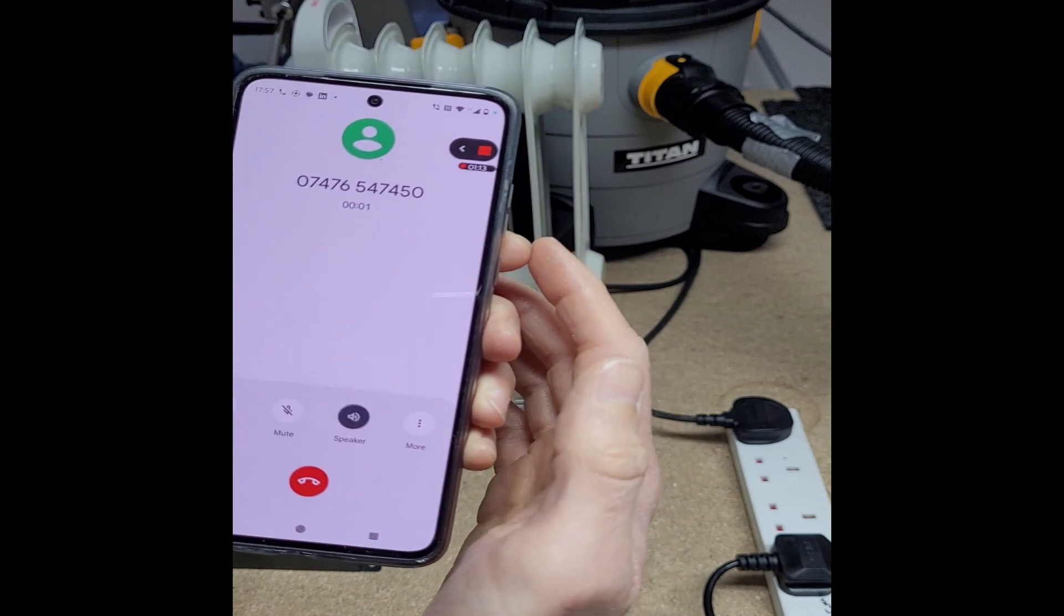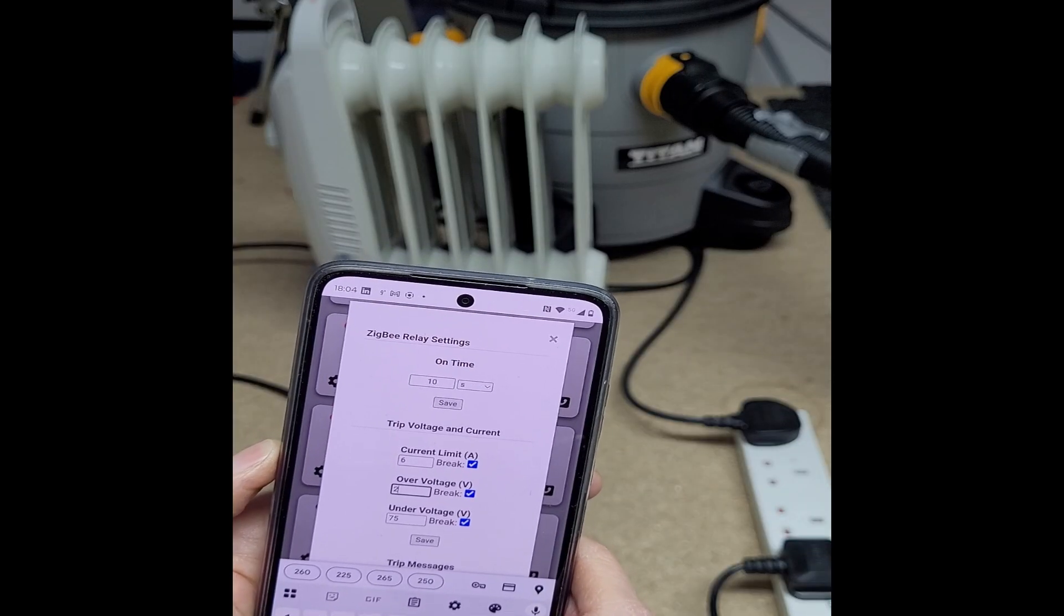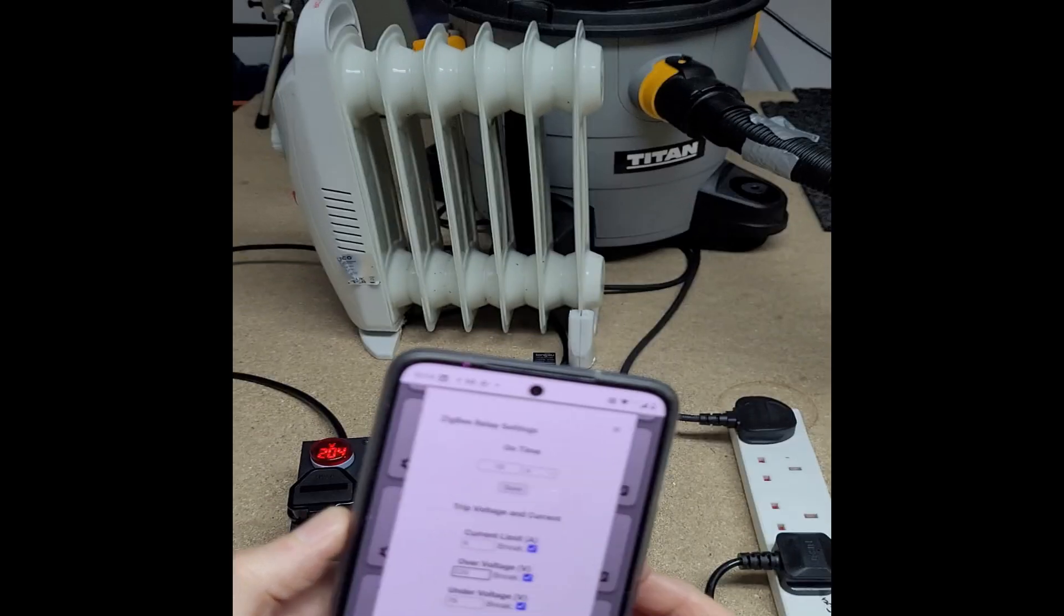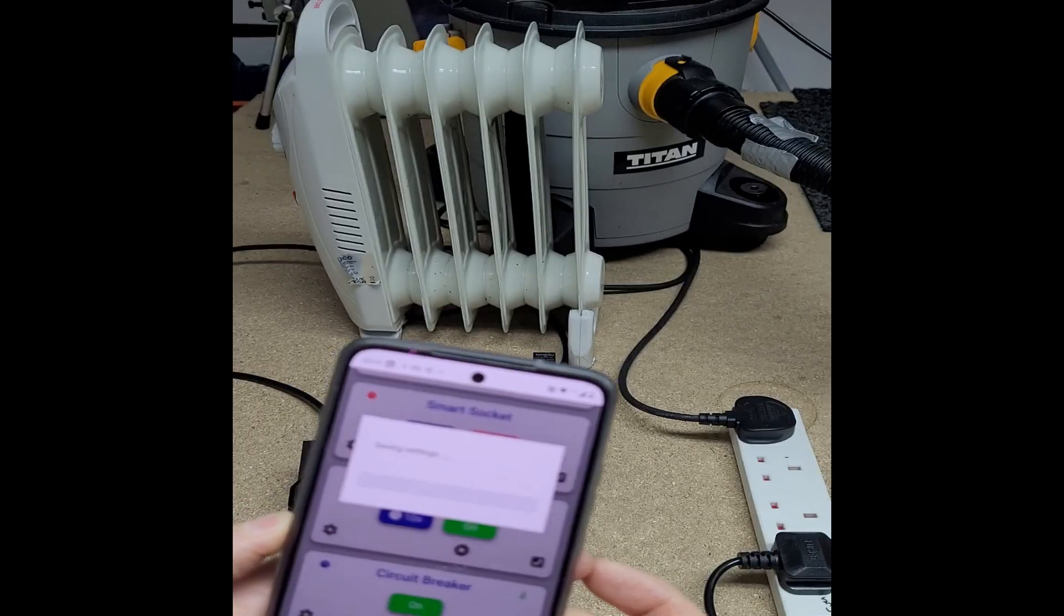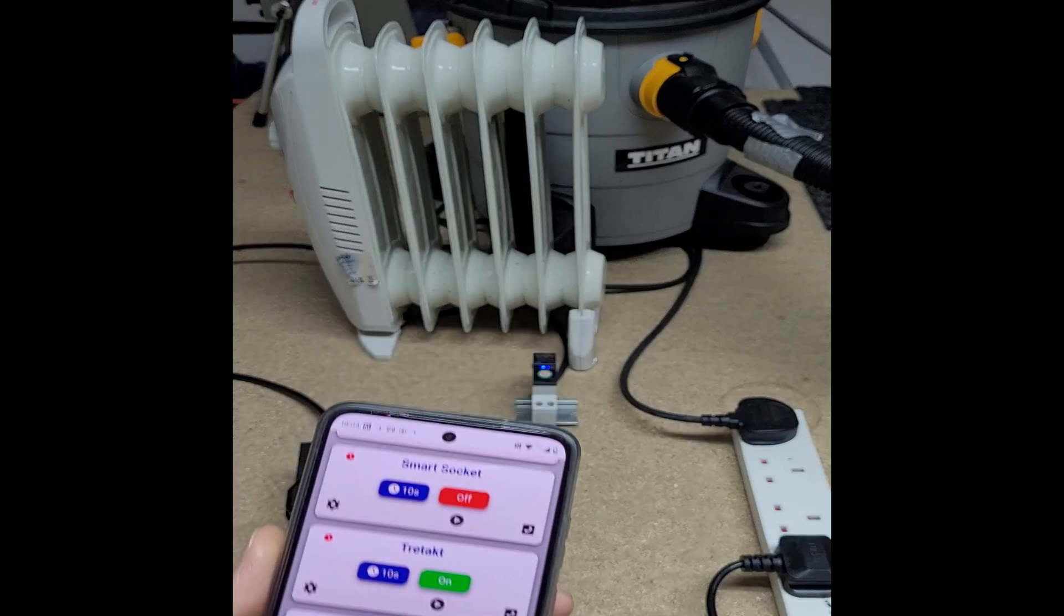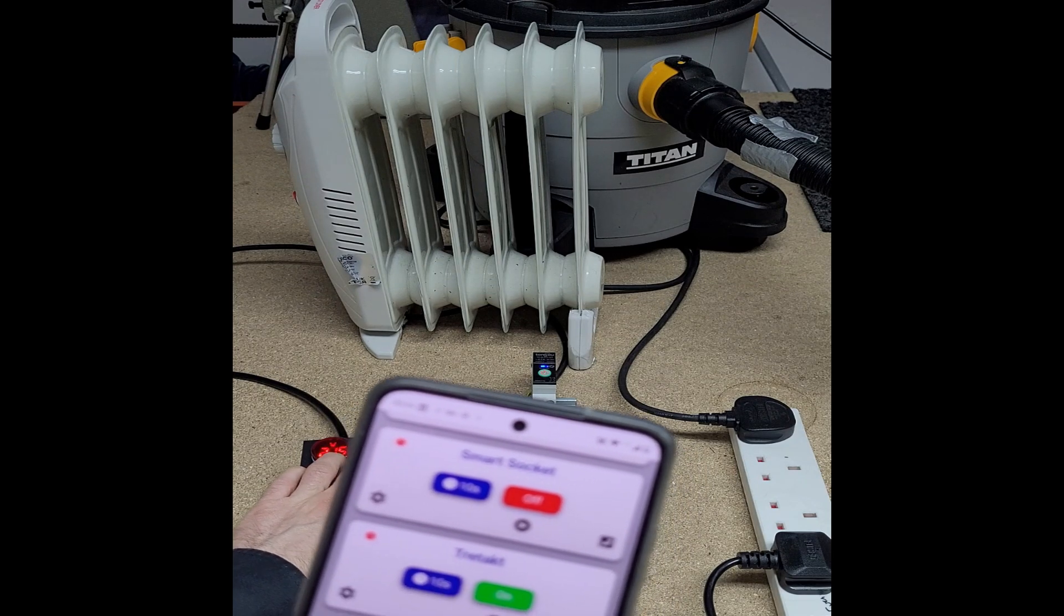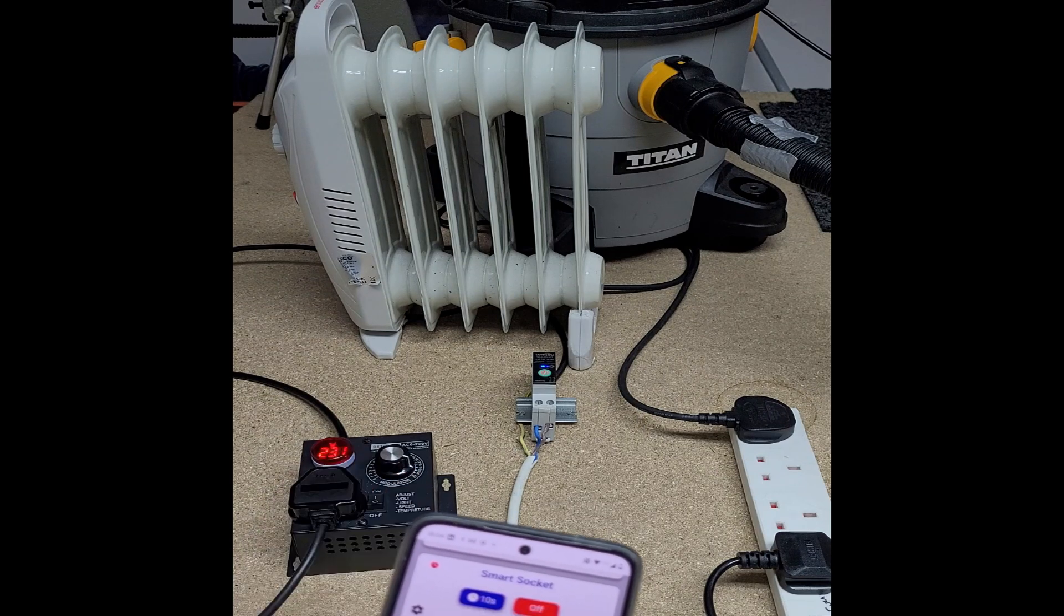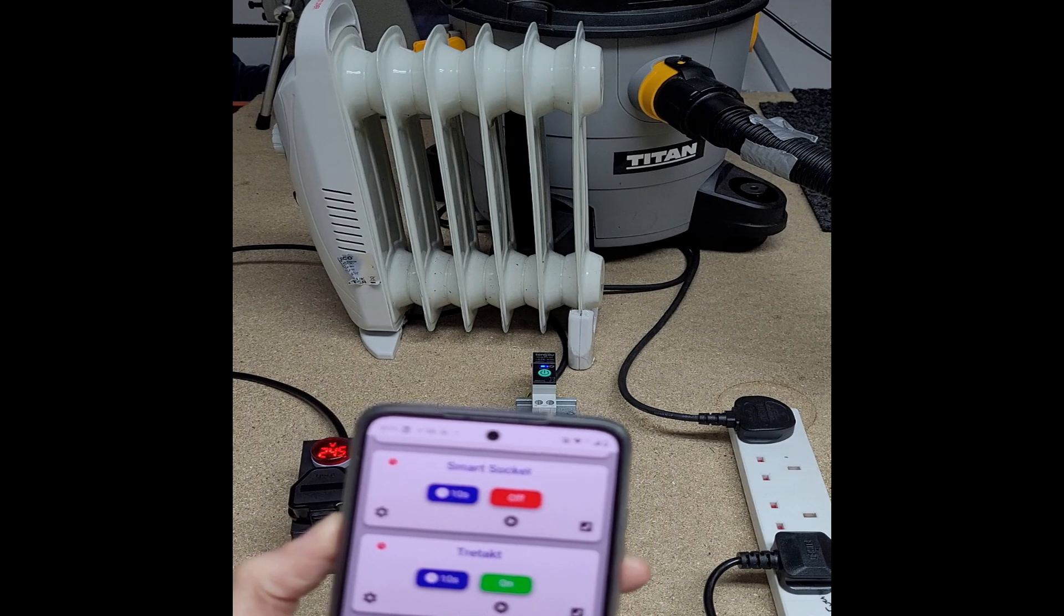Over current. Switch trips over current. I'm going to set the over voltage to 220, so it says about 200 on the triac unit, so I'm going to set it to 220. Okay, that's set now. Now if I increase the voltage on this thing, it will trip out because of voltage. Increase the voltage - there we go, it's tripped out. We get a different message this time.